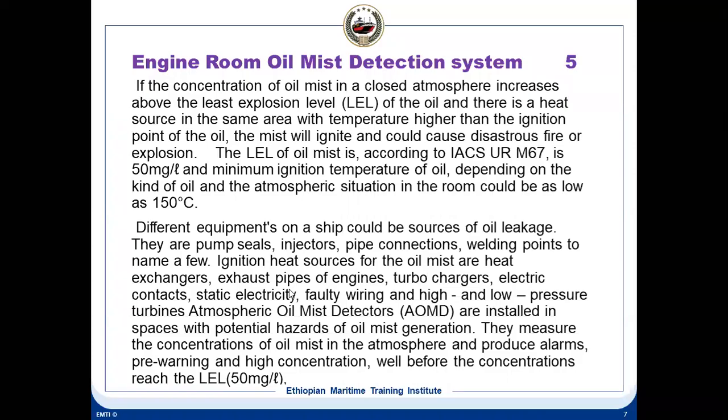These atmospheric oil mist detectors are installed all over the engine room. I will show you the diagram. There are plenty of places where this is located, in such areas where pumps are, like lube oil pumps, or transfer areas. Those areas it is fitted. They measure the concentration of oil mist in the atmosphere and produce alarms. It gives a pre-warning alarm and a high concentration alarm, well before the concentration reaches the lower explosion limit of 50 mg per liter.